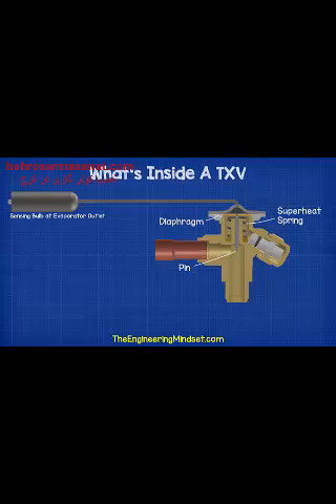Underneath the diaphragm, we have a spring which is pushing up against the diaphragm. We can use this to adjust the superheat, and we'll look at that a bit later in this video. Above the diaphragm, we have this empty chamber which is connected to the capillary tube and then the sensing bulb. The chamber, the capillary tube and the bulb are all hollow.